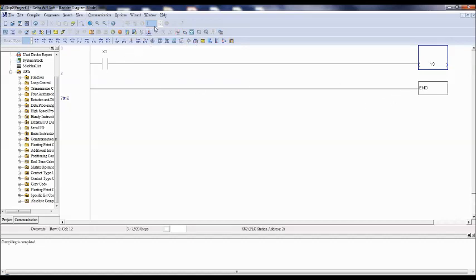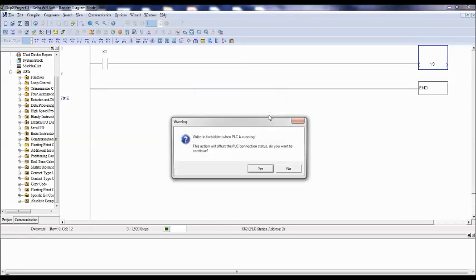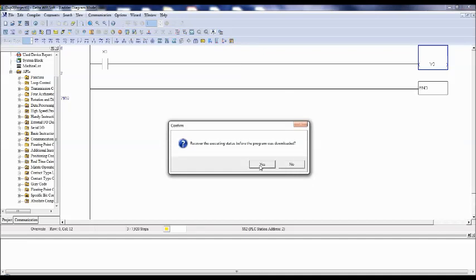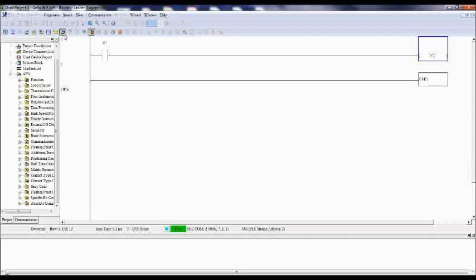Now if communication is established between the PLC and PC, the program must be able to download. In order to download the program to the PLC, the Write to PLC option is there — that is Control F8. Click Download, it is asking do you want to download the program — click Yes. Click Select All for all the options, and then go to the online mode, that is Control F4. So now PLC is in run mode. Whenever you are checking the inputs and outputs of PLC, you should be in run mode.